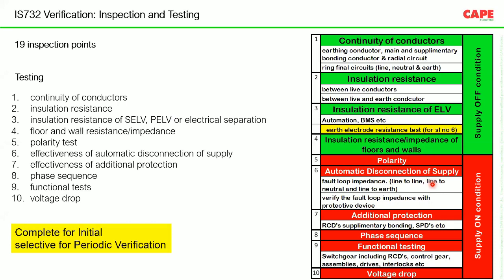Please note that out of these 10 tests, 4 tests don't require power supply; the power supply should be in off condition. And for 6 tests, the power supply should be in on condition, in the sense you need the actual power supply. Here, sometimes we face a challenge. When we go to the client before commissioning the transformer, they say, you come and do a test because now we have a temporary power supply, and with the temporary power supply we are forced to do the test.